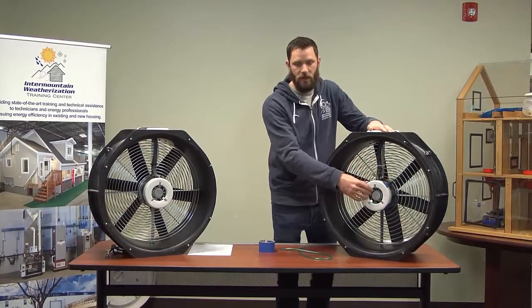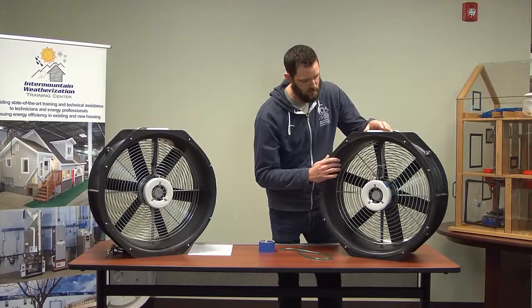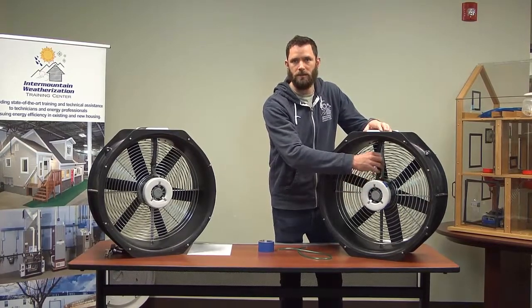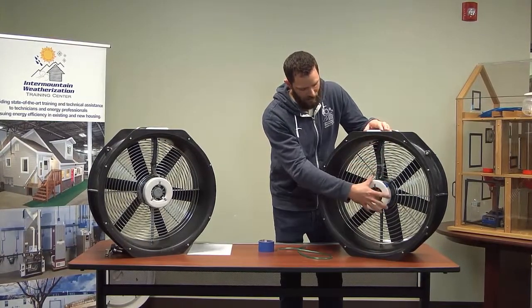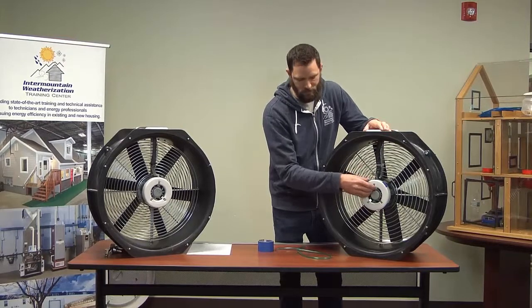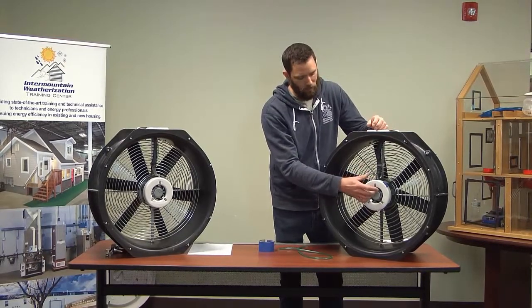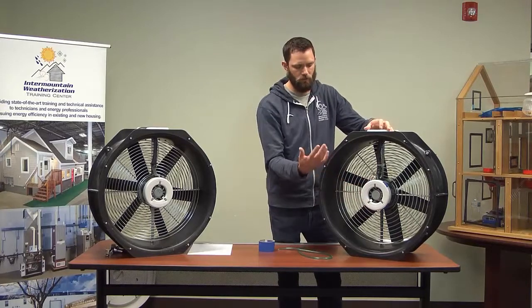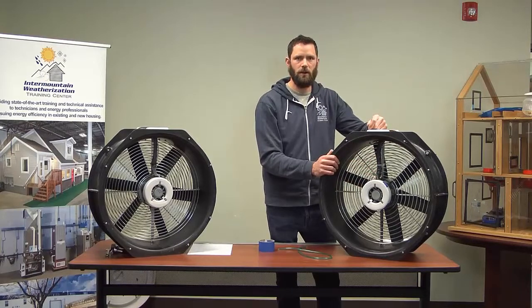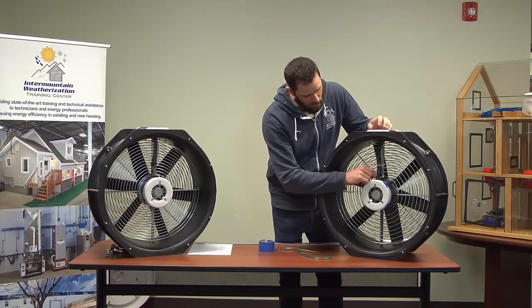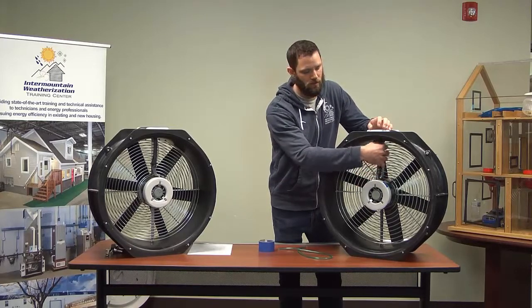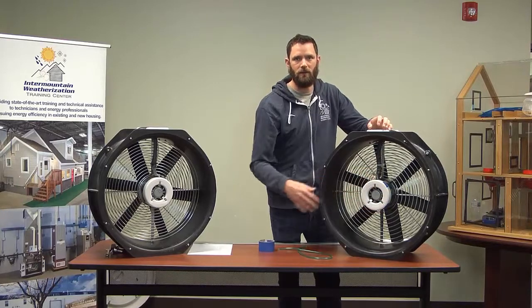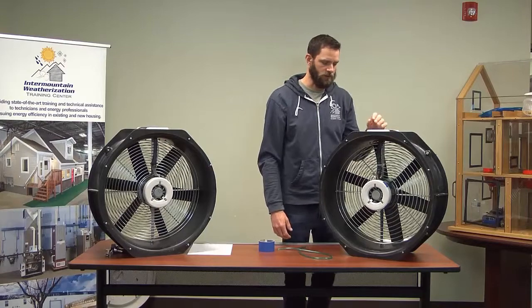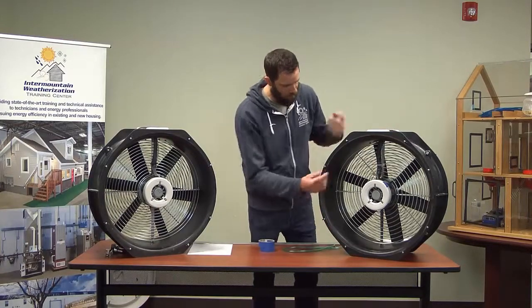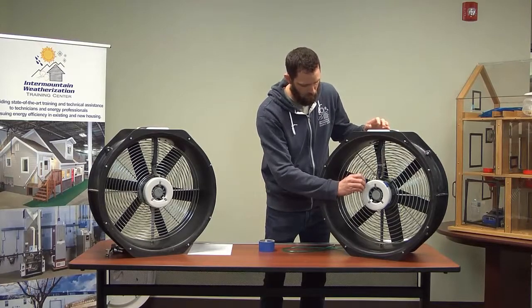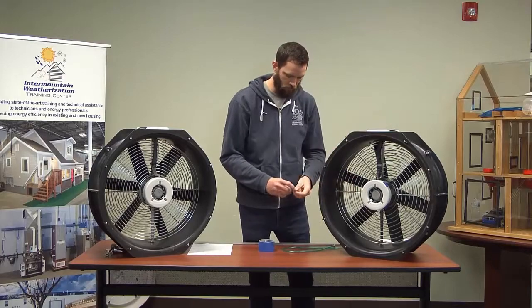If it did not pass the leakage test and I couldn't create a suction that would hold for 5 or more seconds, I'd want to take a deeper look into this hose running up, and also at the sensor housing, to make sure I didn't miss any cracks or anything I could identify. We did reach out to the Energy Conservatory and asked what they suggest if we had a leaky flow sensor, and they said we can change out some of this tubing ourselves in the field. But if the housing is cracked or something, you're definitely going to have to reach out to them and probably get some parts to fix the problem. So just be aware of that, and make sure after you finish this test that you uncover the flow sensing ports.